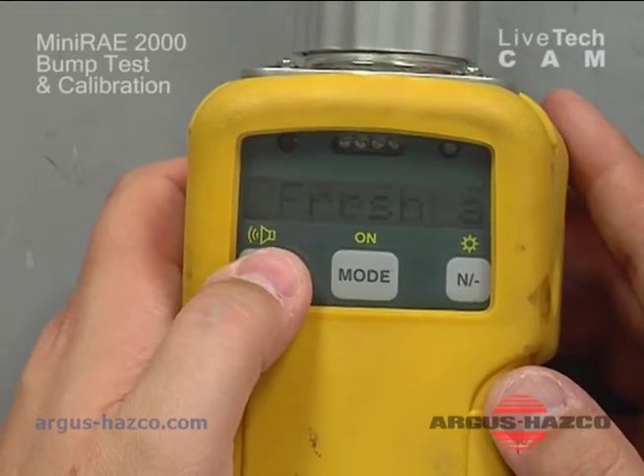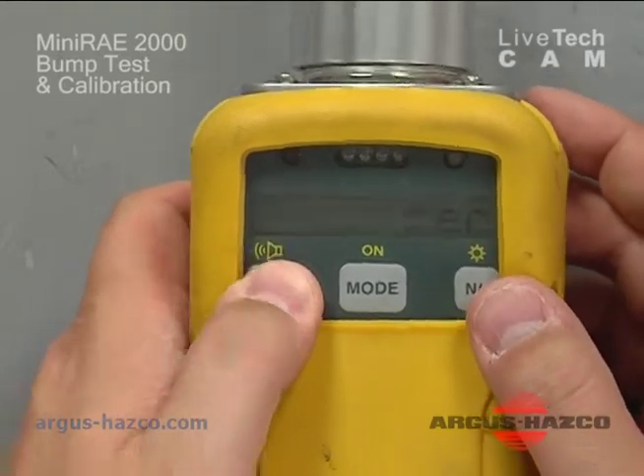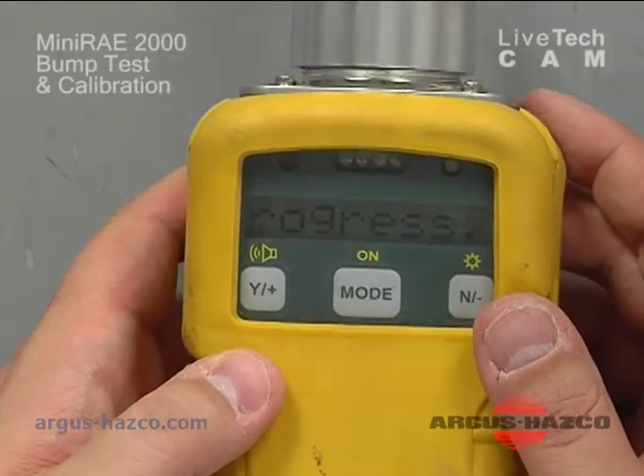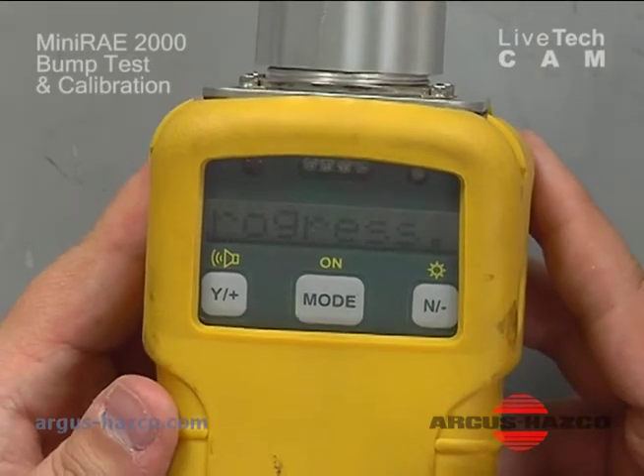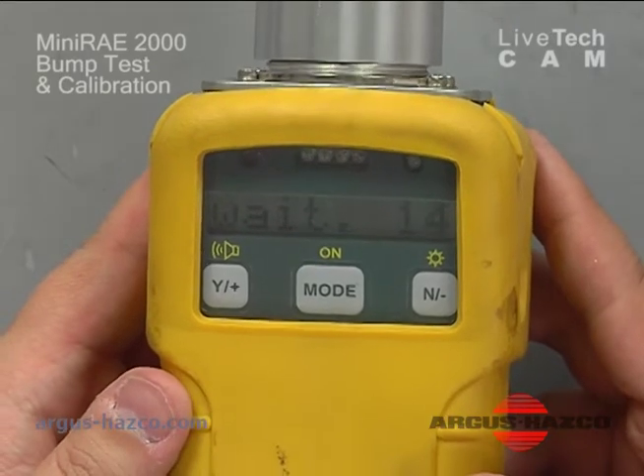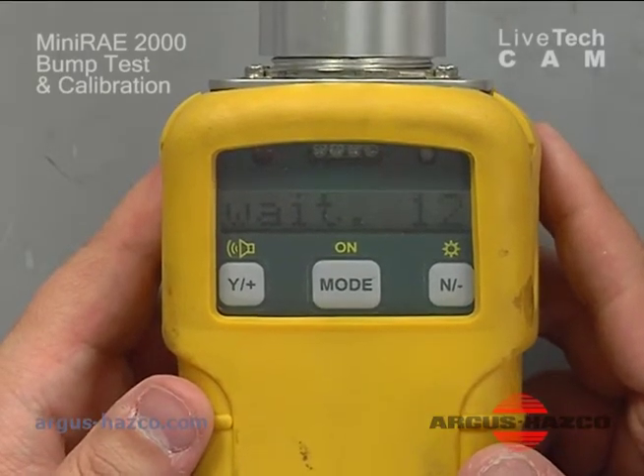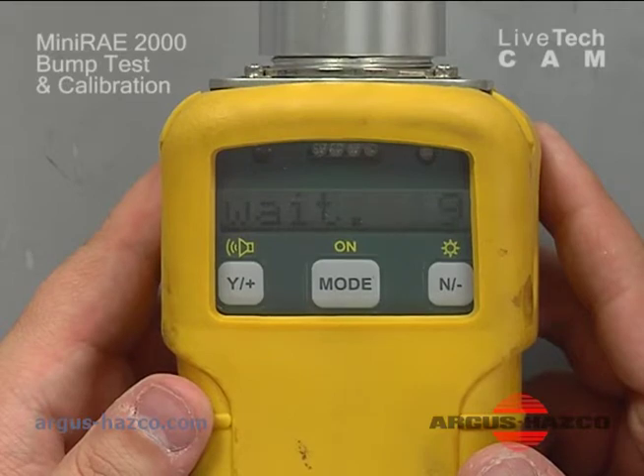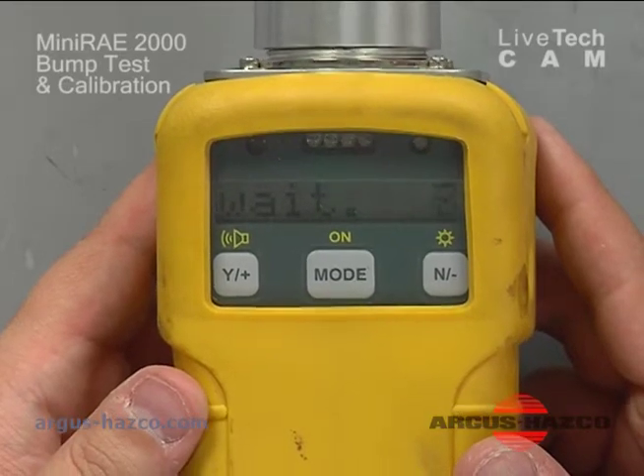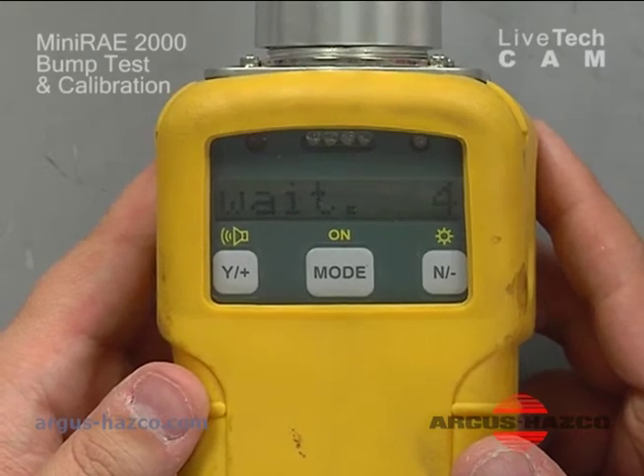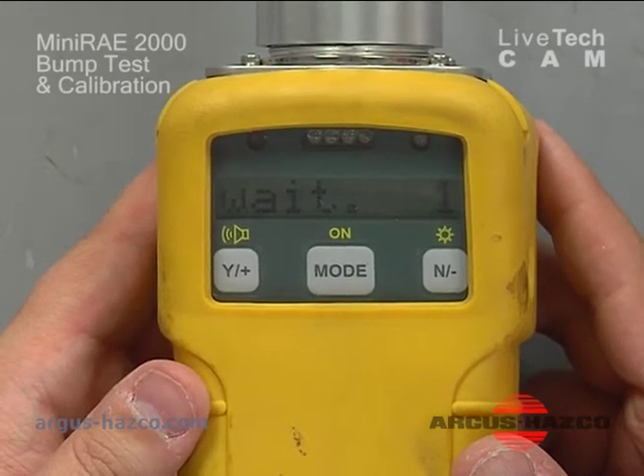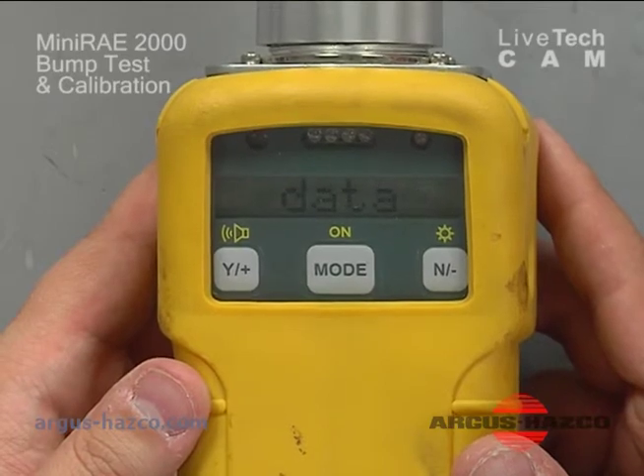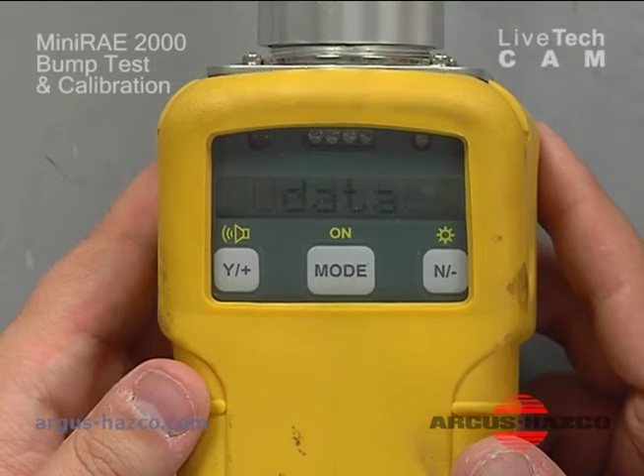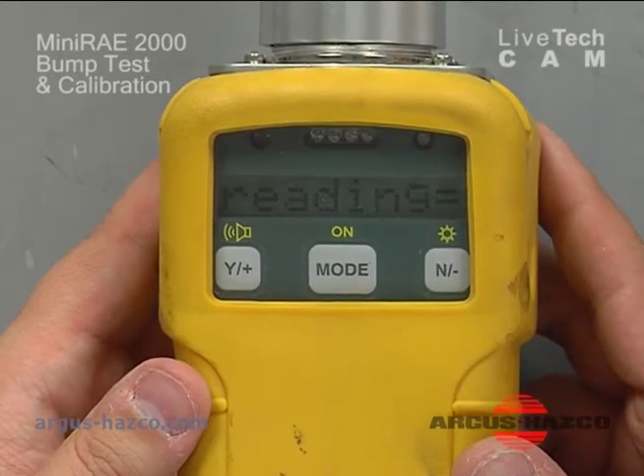Fresh air cal. We'll do a fresh air cal again. Zero's in progress. Wait 15 seconds. The reason why you want to do a second zero is because with that being so high, you want to ensure that you do have a true 0 point before you calibrate. It's updating the data. Reading is at 0.